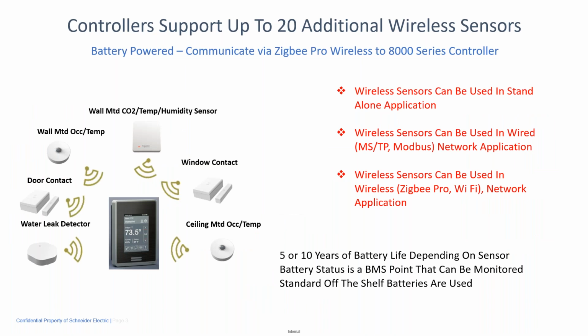The controllers themselves also support the capability to add up to 20 wireless sensors that can communicate via Zigbee Pro wireless to the 8000 series controller. So you could add occupancy sensors, you could add a door contact, a window contact, water leak detectors, or a remote temperature, humidity, CO2 sensor. Those are all battery-powered devices. There's anywhere from 5 to 10 years of battery life, depending upon which sensor is chosen.